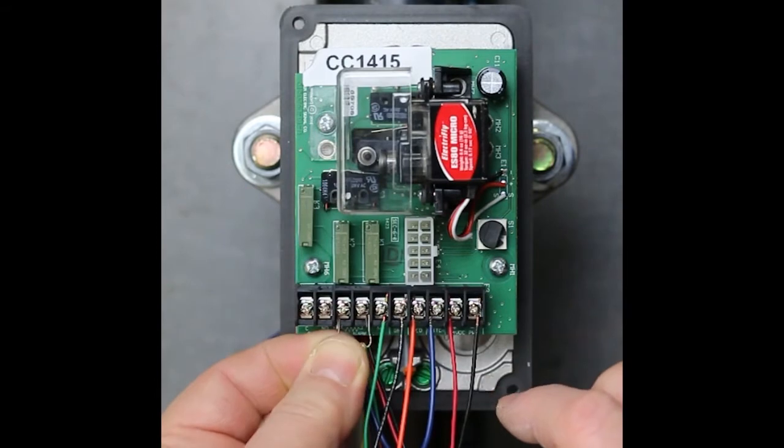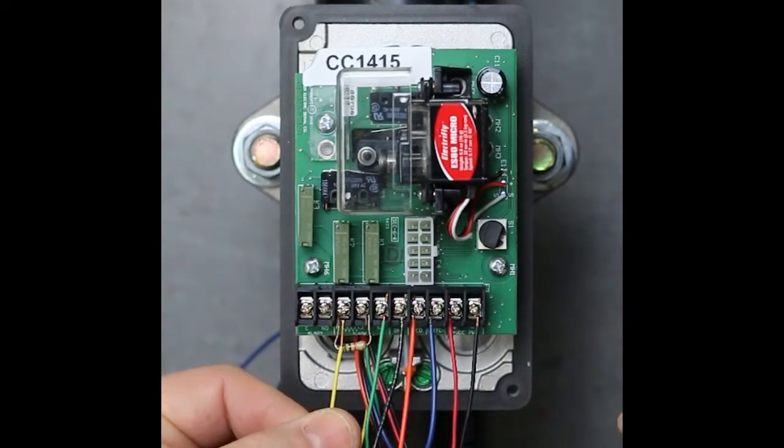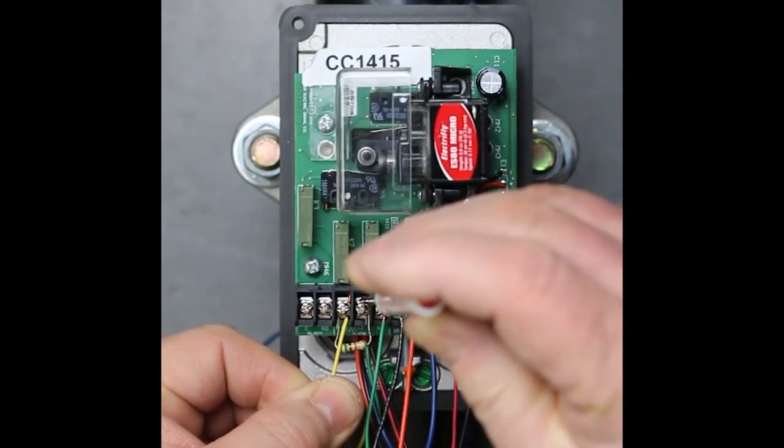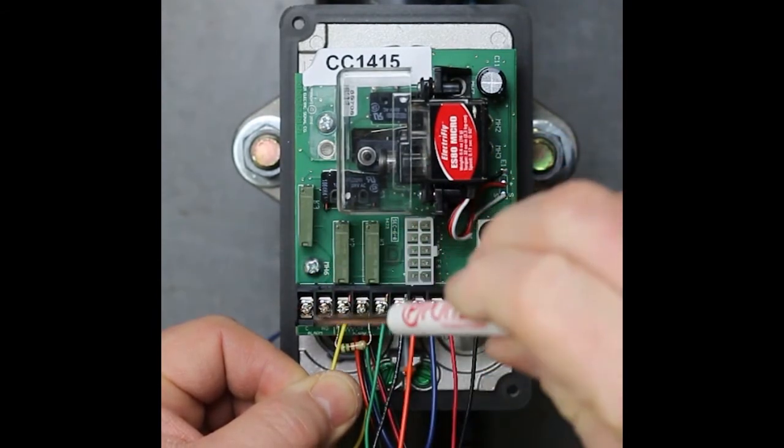The two wires from the fire alarm panel or addressable module connect to the terminals marked C and NO. The end of line resistor from the panel connects to the terminals where the resistor symbol is shown on the board, the C terminal and the one immediately to the right of it.